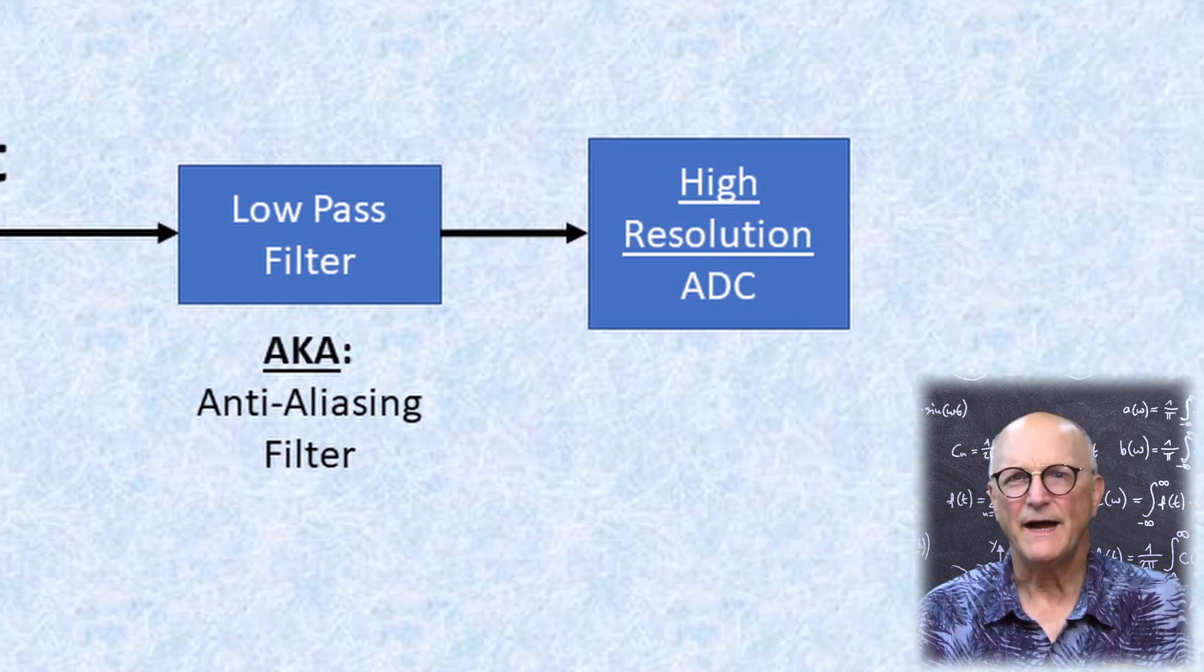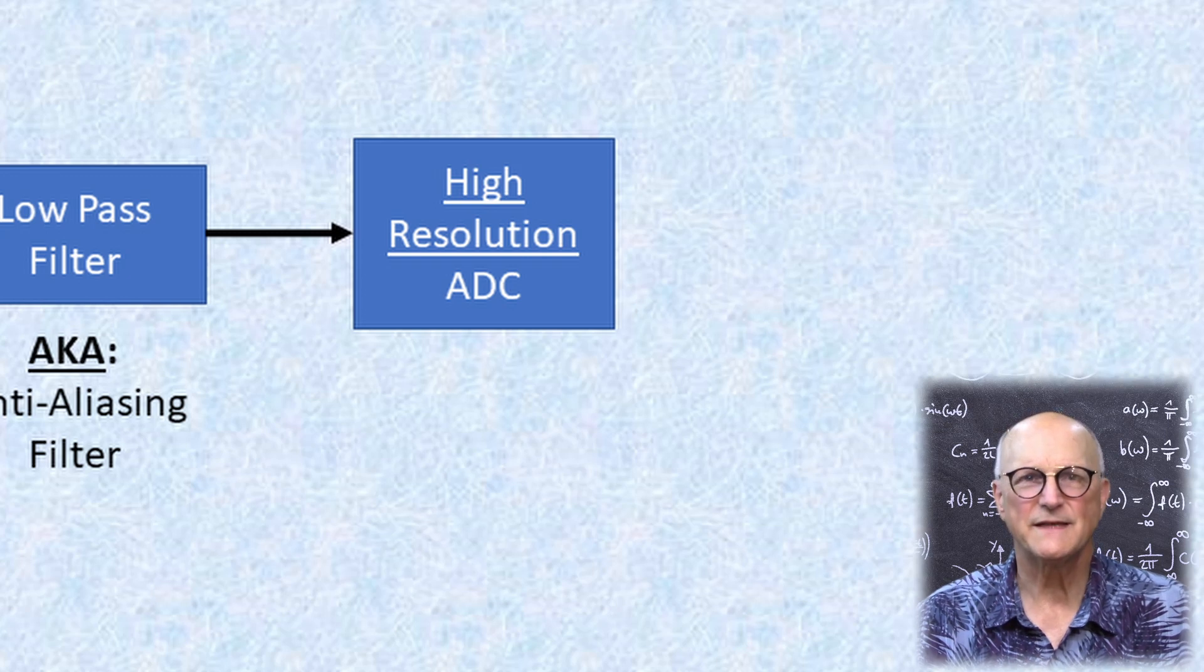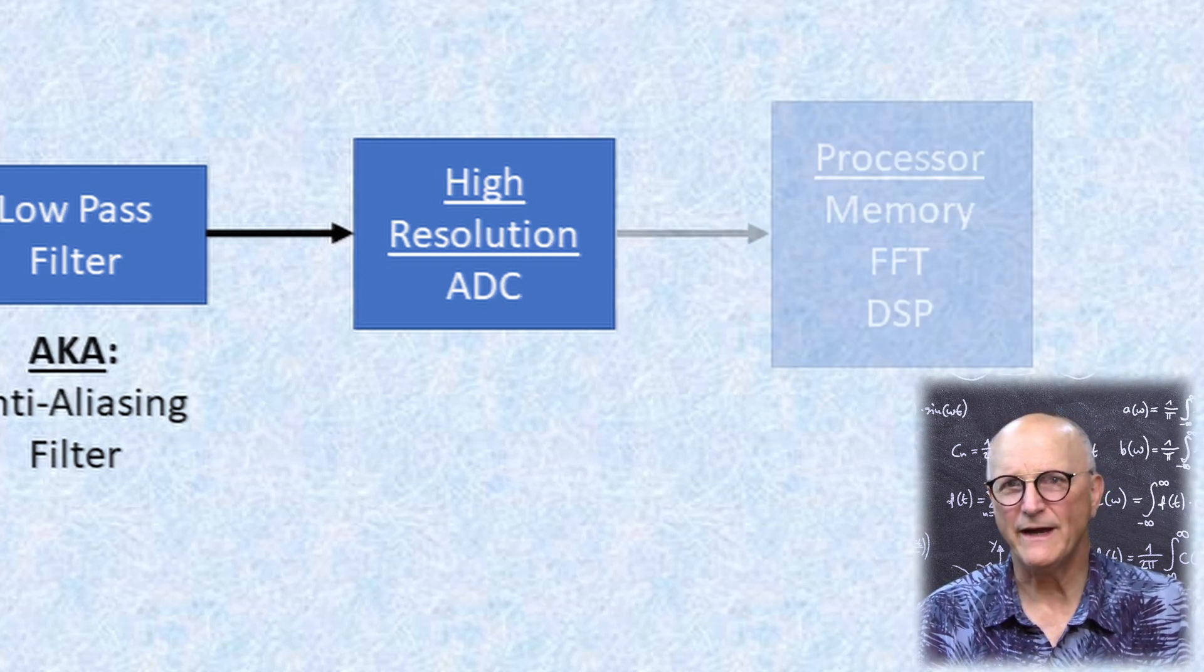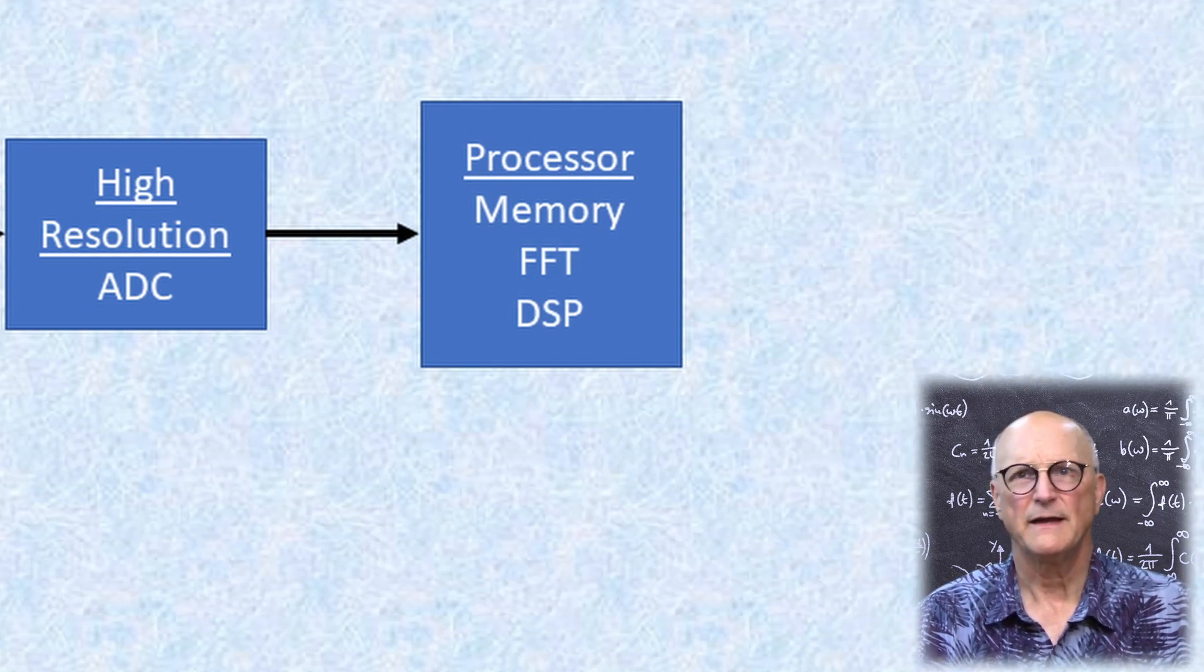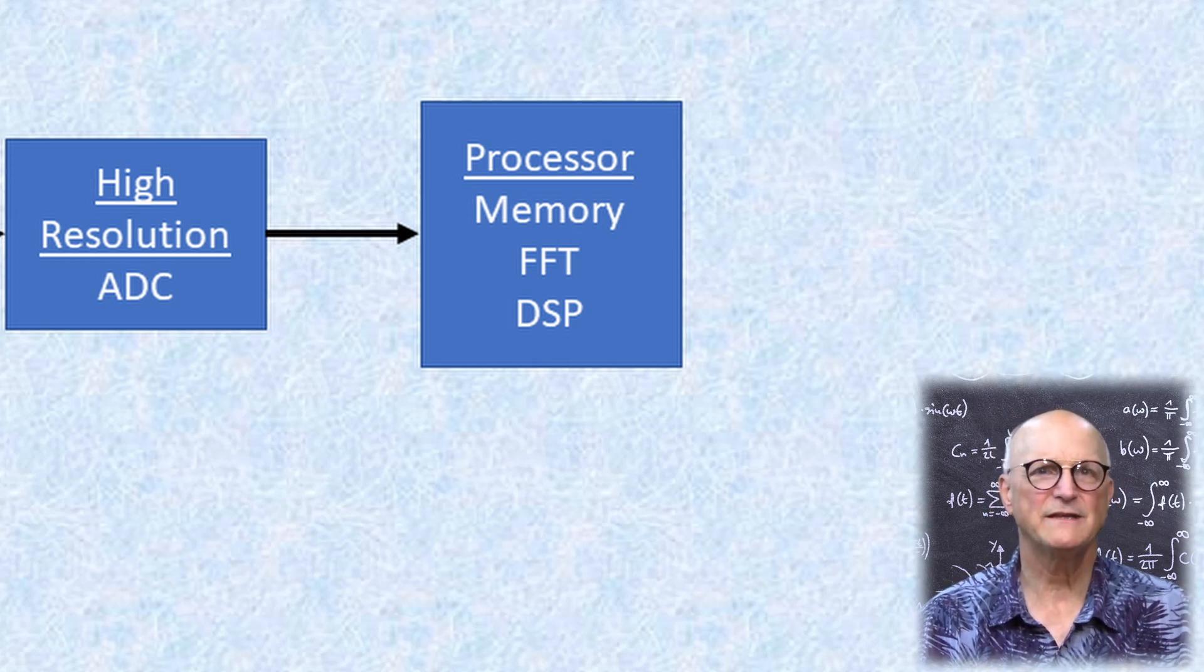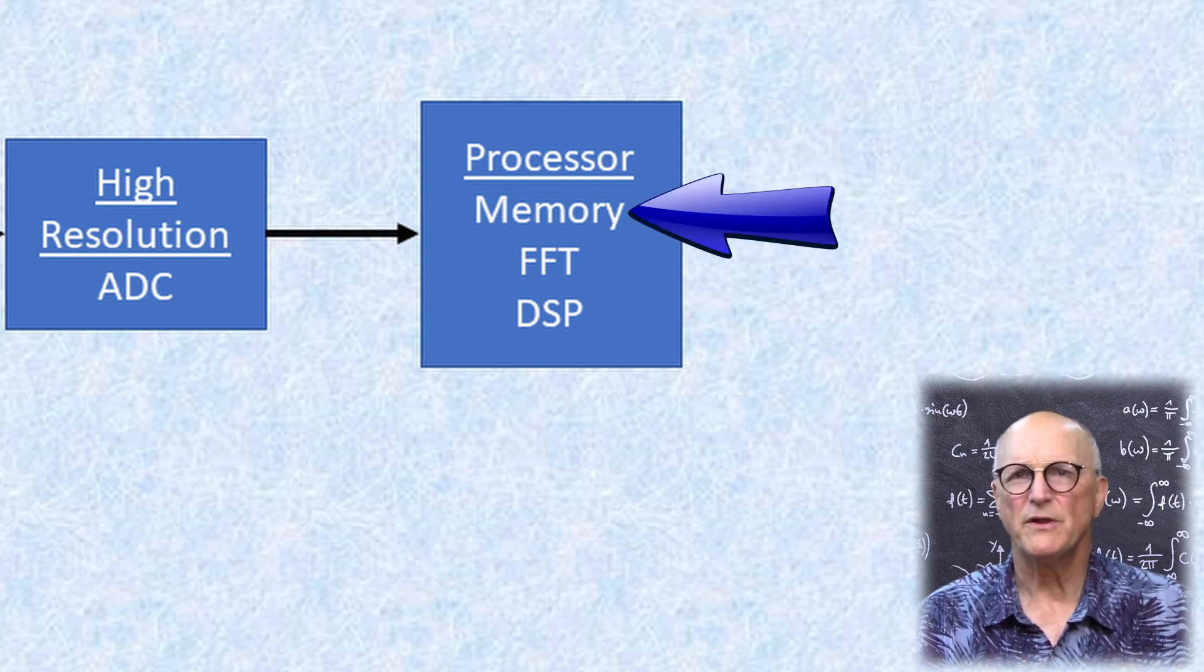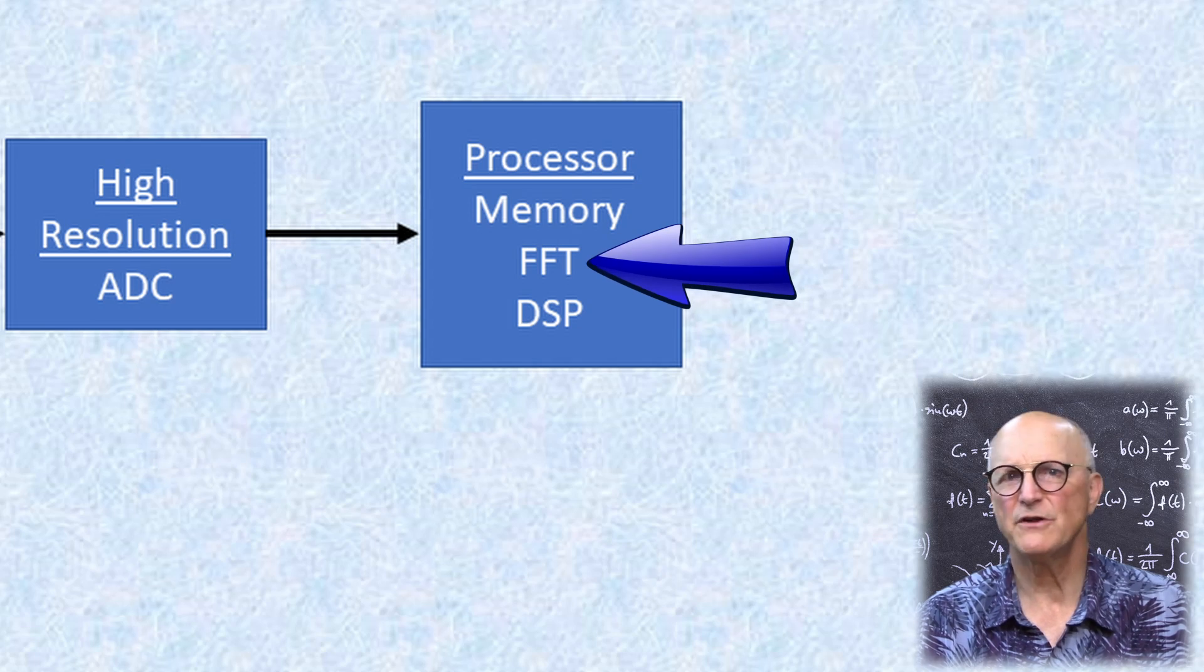We then come to the high-resolution analog-to-digital converter or ADC, which samples the time domain data at a fixed rate and provides these samples to the processor. The ADC samples are placed in memory, and then the processor performs the fast Fourier transform or FFT on this data.